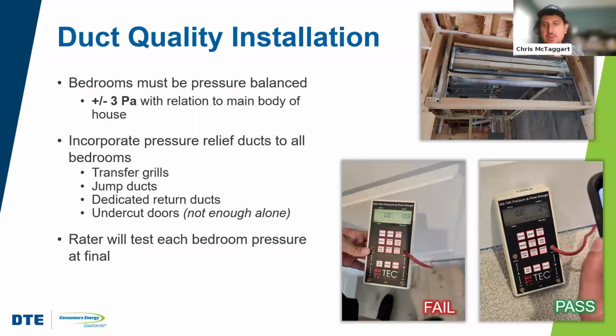So other requirements, irrespective of track, is that bedrooms have to be pressure balanced to plus or minus 3 pascals with relation to the main body of the house. For those of y'all who don't really understand what this means, a pascal is a unit of pressure measurement, and 3 pascals is a pretty small number. But the goal is that, in homes, people typically have bedroom doors closed at nighttime. Why? Well, because people want privacy at night. Because of that, if the home does not have a balanced return and supply in each one of those bedrooms, then when you close that door, any stagnant air is not able to make its way back to a return so it can be reconditioned.